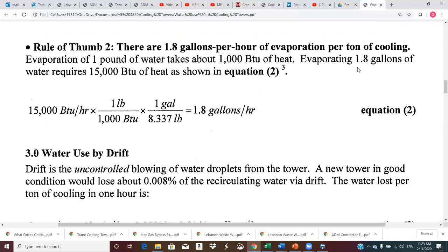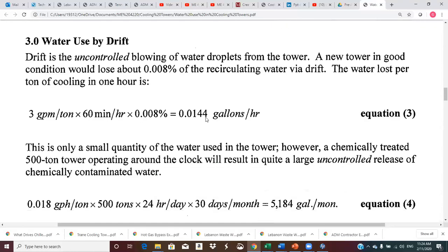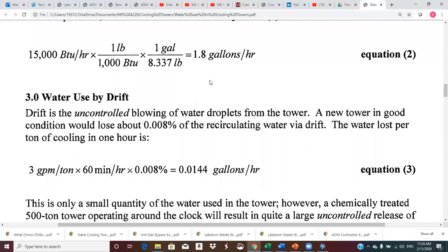So evaporating this 1.8 gallons requires 15,000 BTUs of heat, as shown by equation 2. And so if you take the 15,000 BTUs an hour, which would be 1 ton, and divide it by 1,000 BTUs per pound, and then divide by 8.33 to convert into gallons, we get 1.8 gallons per hour. So that's interesting. So we can use that given the tonnage.